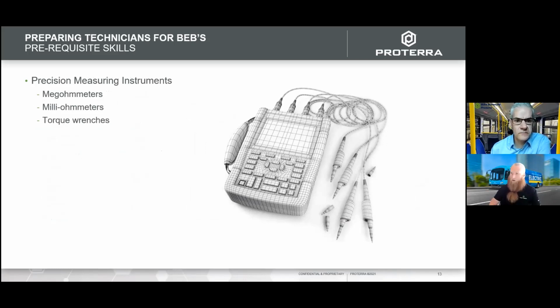Building on our tools discussion, I also want to throw in the prerequisites for precision measuring instruments. It's not as common that technicians will need to use these, but it's a skill they need to have: megohmmeters, milli-ohmmeters, and torque wrenches, and I'd also add oscilloscope use as beneficial. Megameters are electric meters that measure very high resistance values by sending a high voltage signal into the object being tested, typically used for testing breakdown of insulation. It can test the breakdown of insulation in electric motors to determine whether they're about to fail—basically, if they've had that wear in their life, it's time to either rebuild if possible or simply replace.